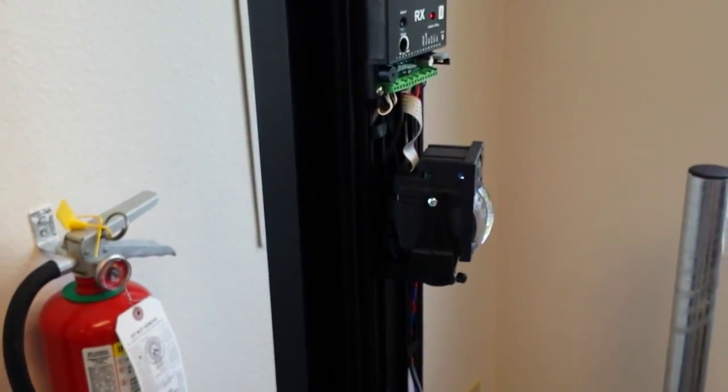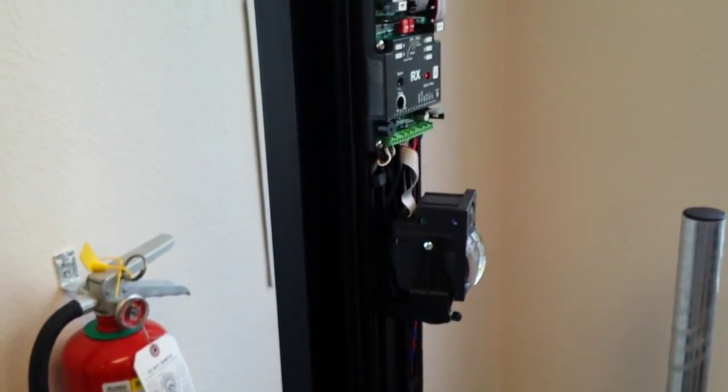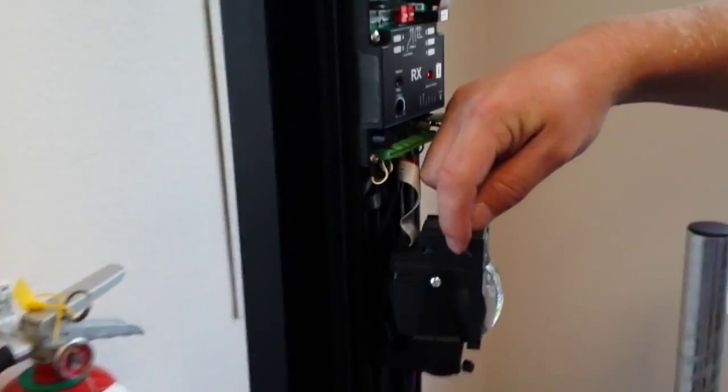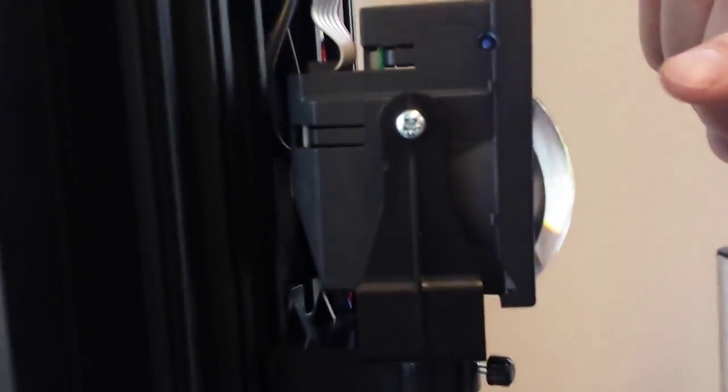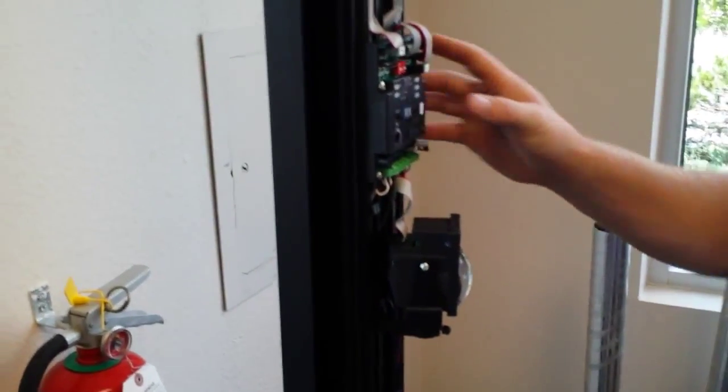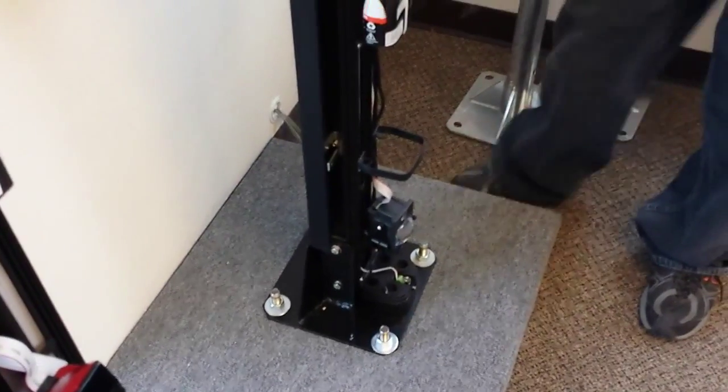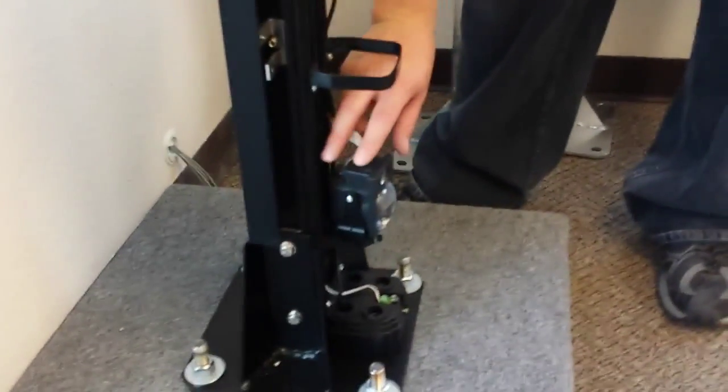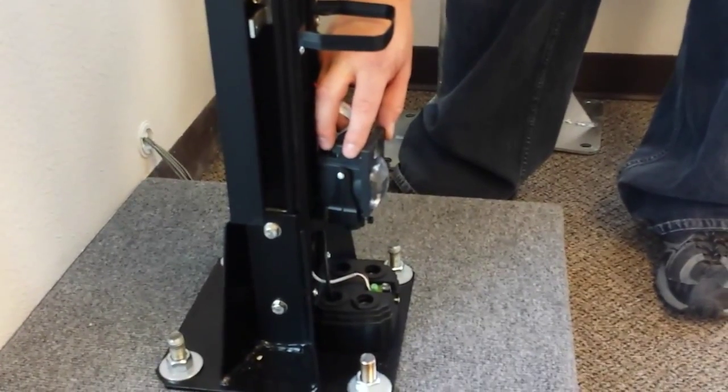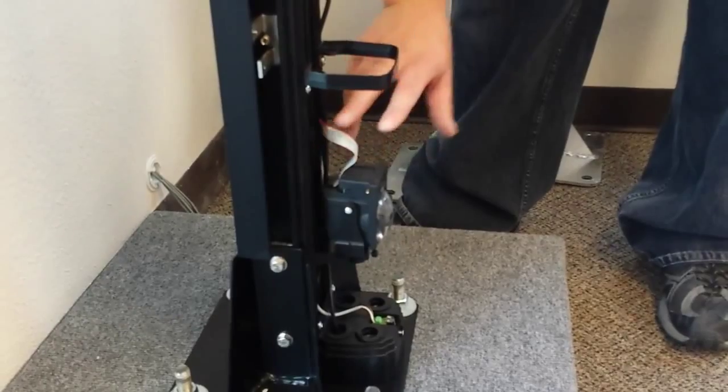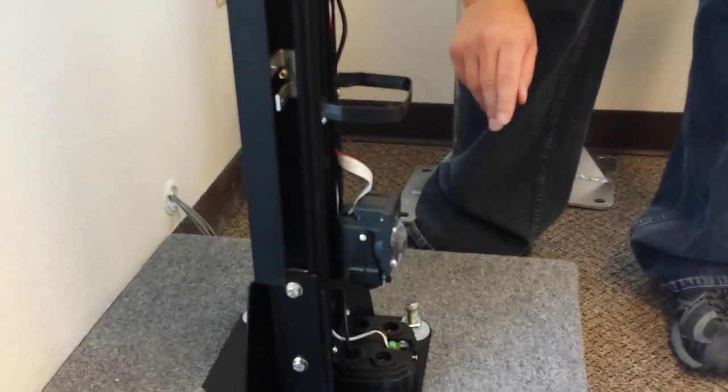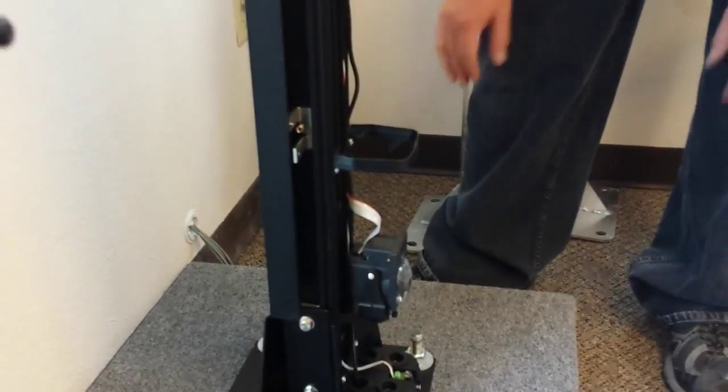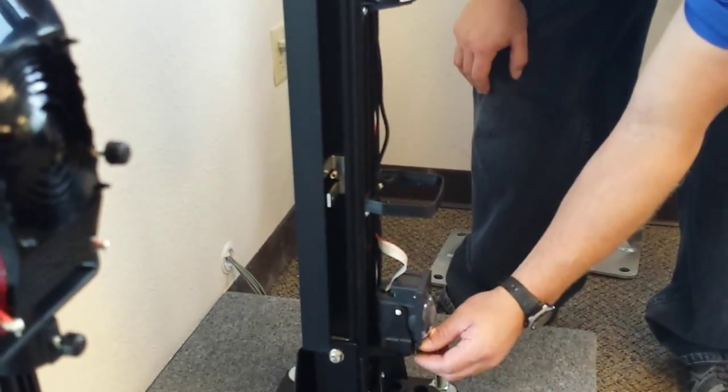When we're aligning these we have two tools for alignment. We have a visual alignment right here on the side. It's on both sides with a 45 degree mirror in there so it shoots out the front and you get a visual alignment. And we also have an audible tone. So one beep means we're on cell number one, and the beep speeds up as you get closer to alignment. When you have solid tone, that's the best alignment you can get. If you can't get solid tone, get as close to it as you can and tighten the set screw.